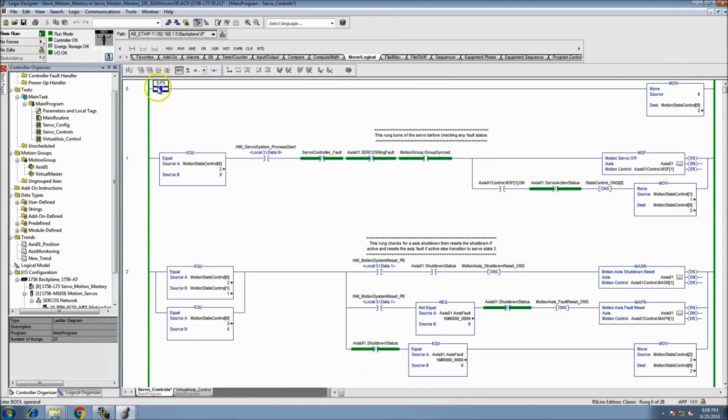But just to show you, if this fires, it's just going to load a 0 into my state machine, or into my array, or whatever value you choose to use it on. You don't have to use this on just a state machine. You can use this on whatever value you choose. Say, for instance, you have speed controls, or any value that you want to set to 0, or set to a known factor or constant somewhere in the program based upon system initialization. Then this is what this first scan bit is used for. You can also put in a first scan hold, like putting in a timer and jumping around the timer to make that happen.